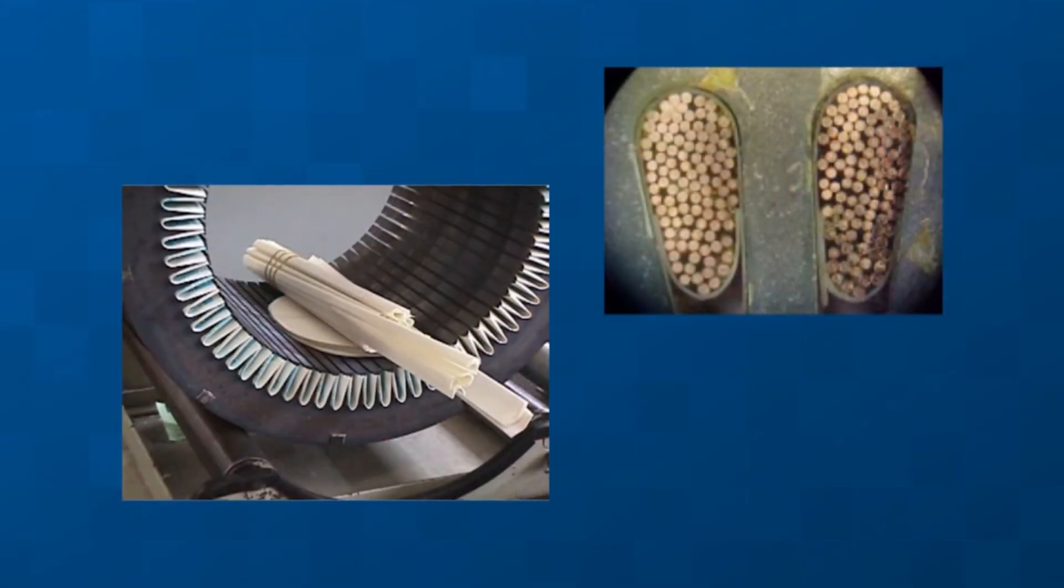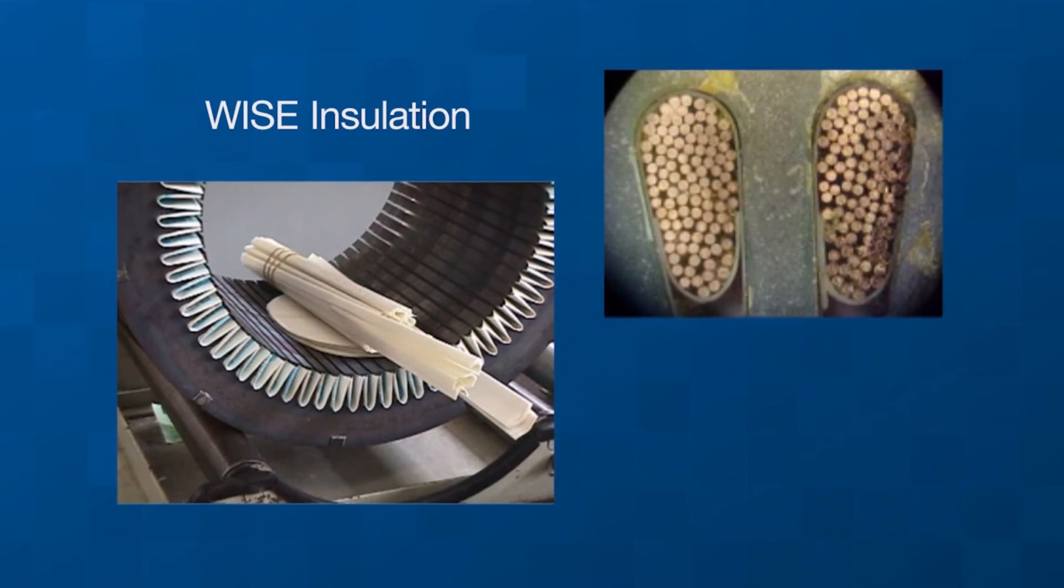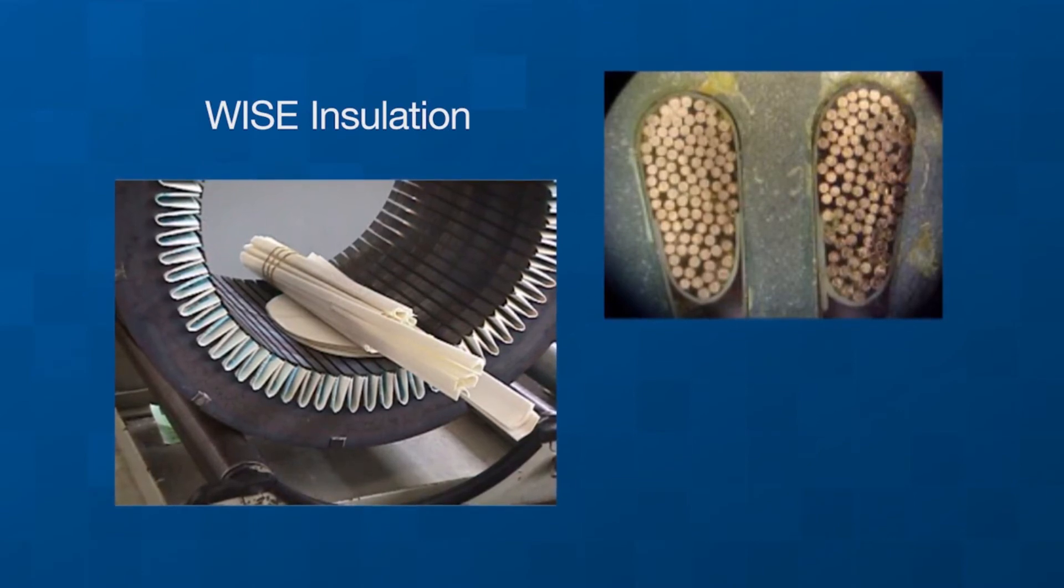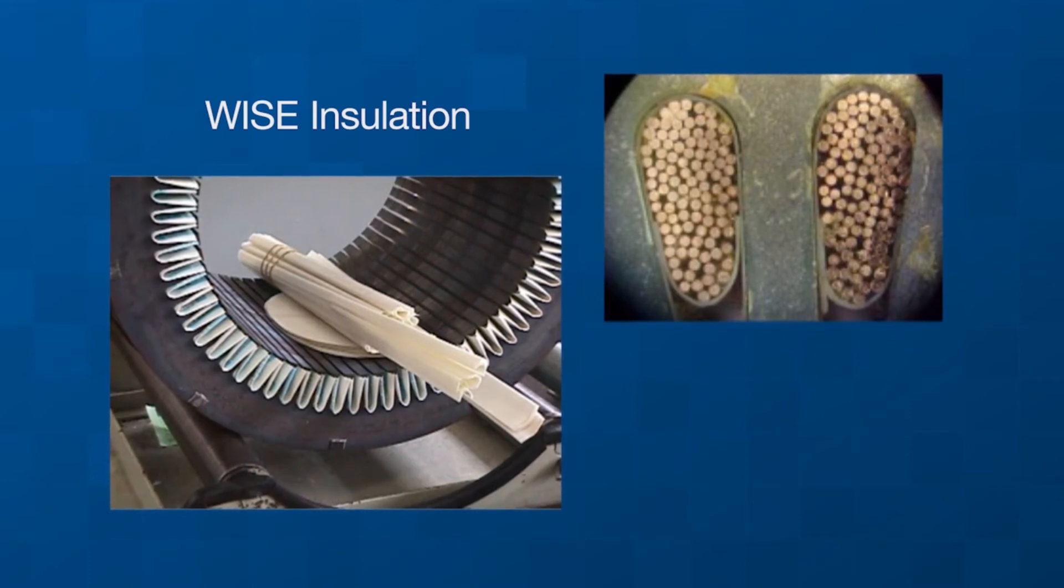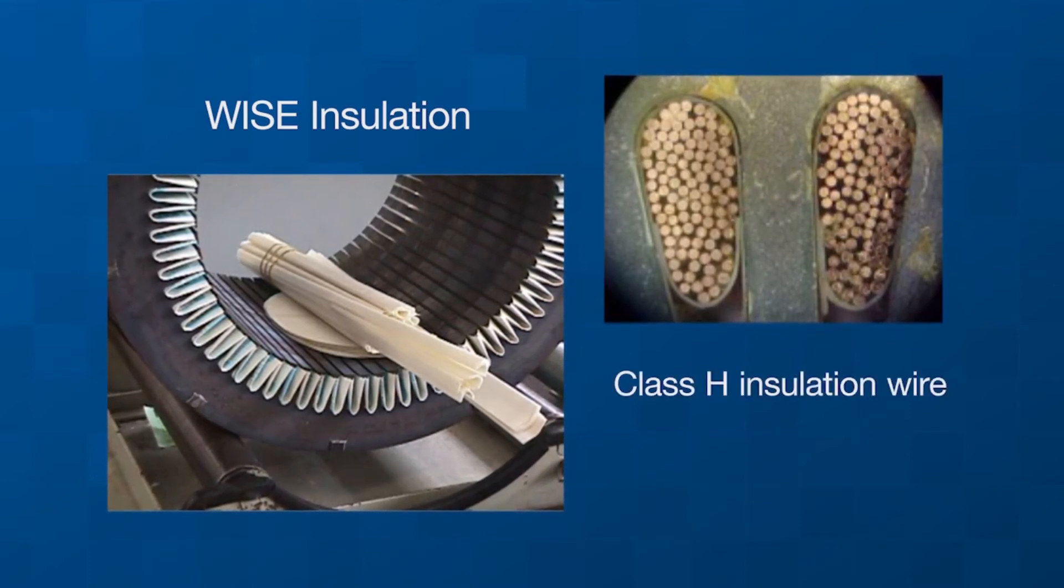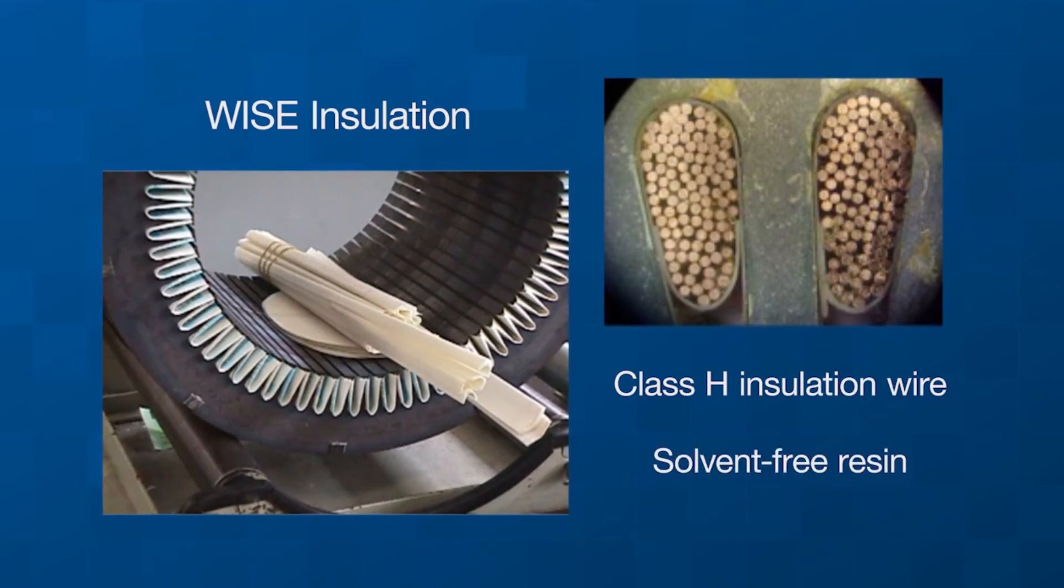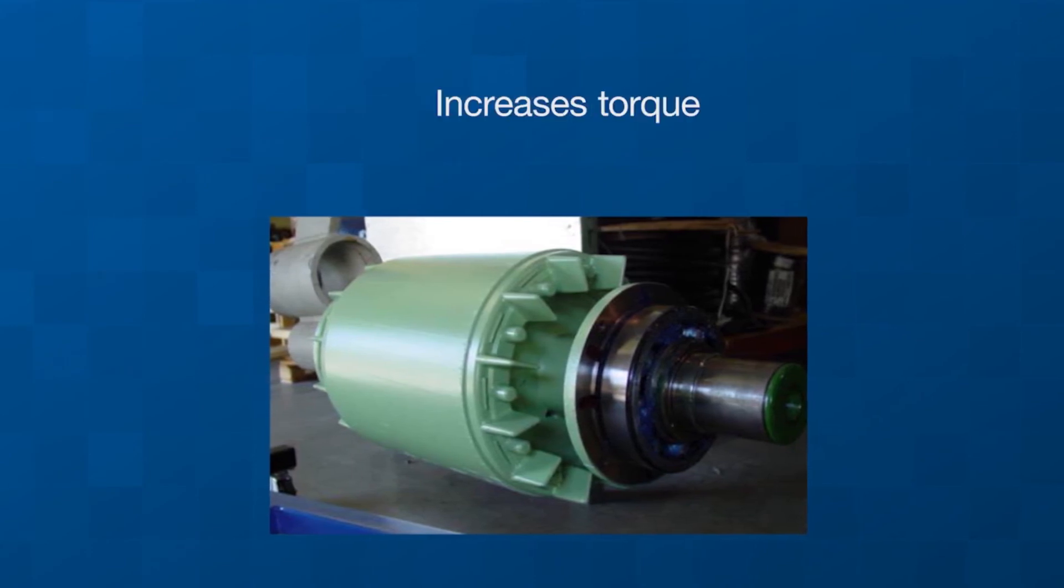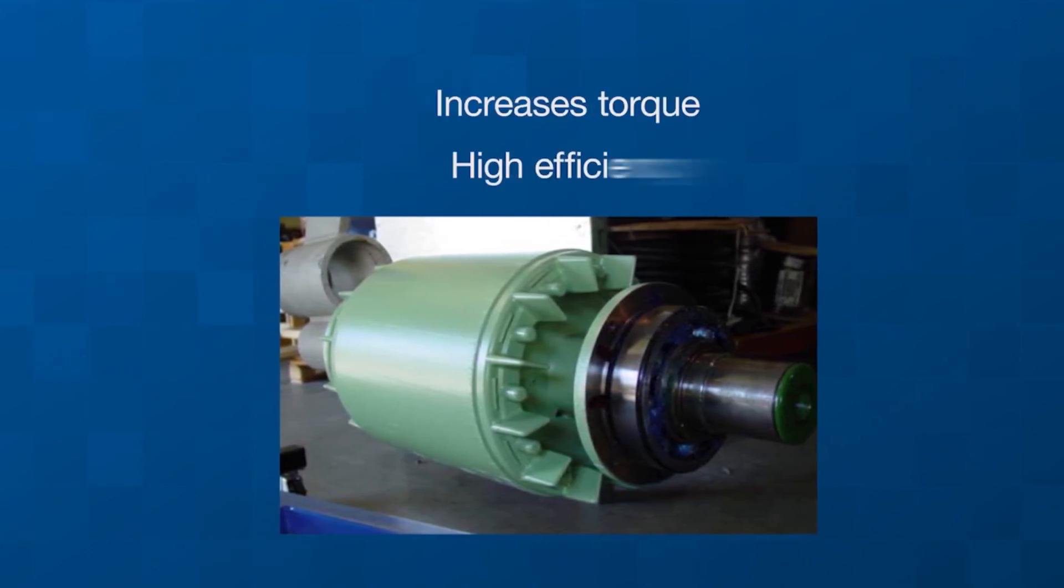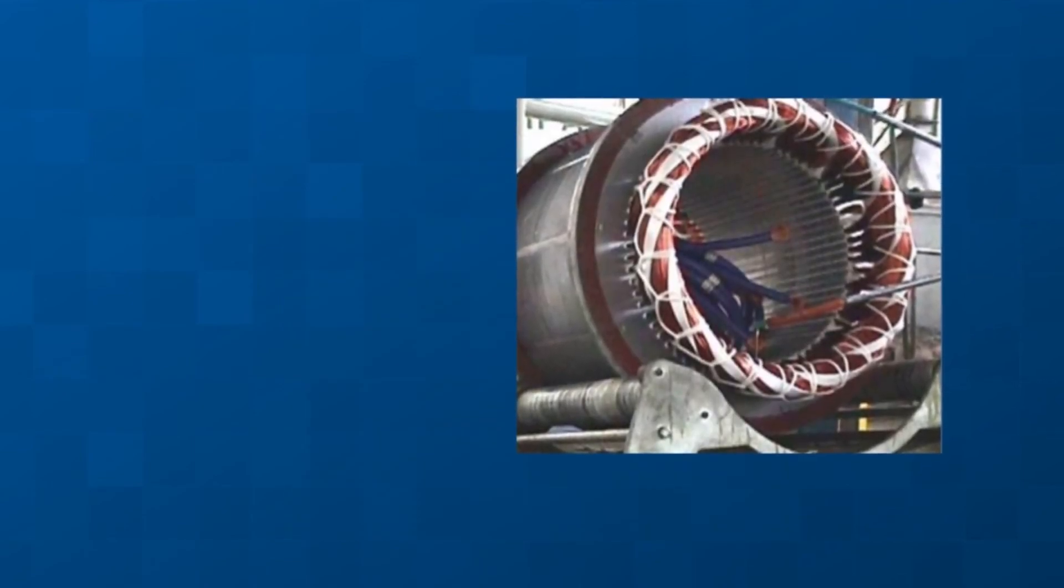All W22 motors are designed with a WISE insulation system, WEG insulation system evolution, permitting them to be driven by a VFD. This continuous flow system is composed of Class H insulation wire and a solvent-free resin, eliminating any trapped air bubbles. The rotor's cast aluminum construction increases torque, and the stator windings provide high efficiency. Both coil heads are securely laced for added strength.